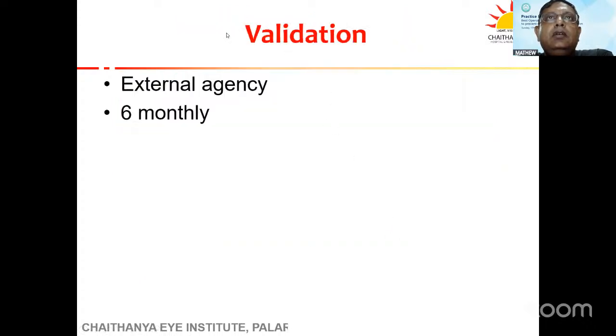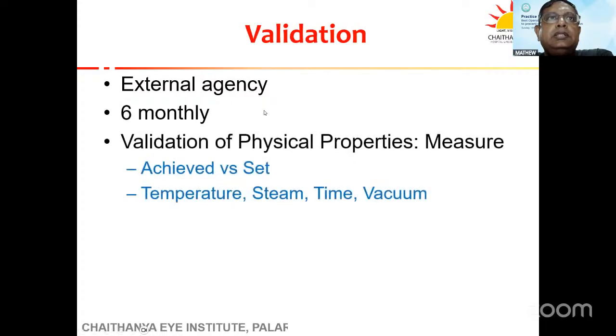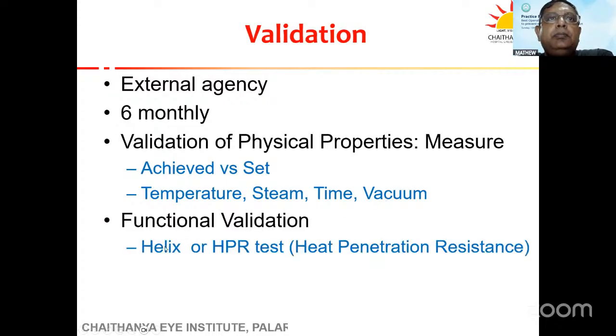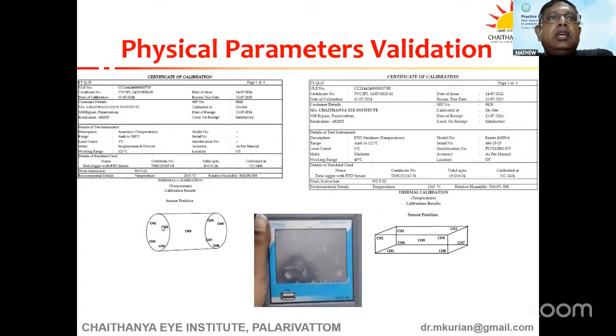The validation of these things is very critical, and it's better to get it done by an external agency. NABH requires it 6 monthly, and what is tested is to see whether what is achieved is what is set in terms of temperature, steam, time, and vacuum. And functional validation can be done by the helix or the heat penetration resistance test. So here inside the chamber at 9 points, this kind of resistors are placed, and the thermal calibration is performed. This is for the ETO, and this is for the steam sterilizer.